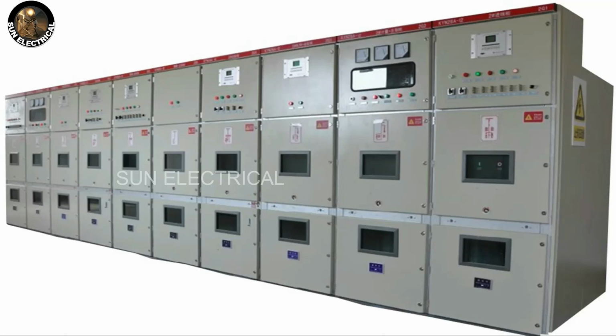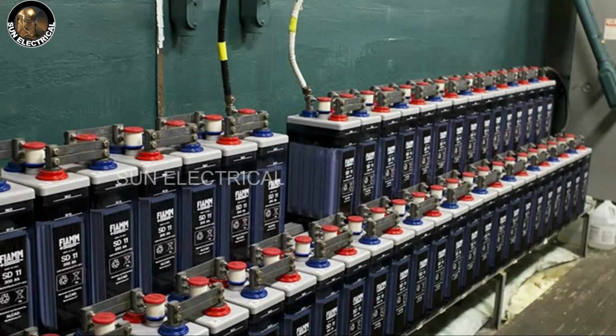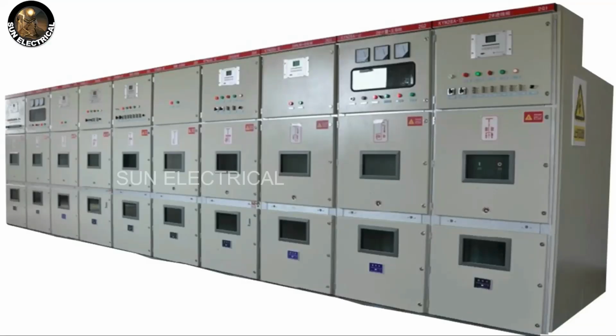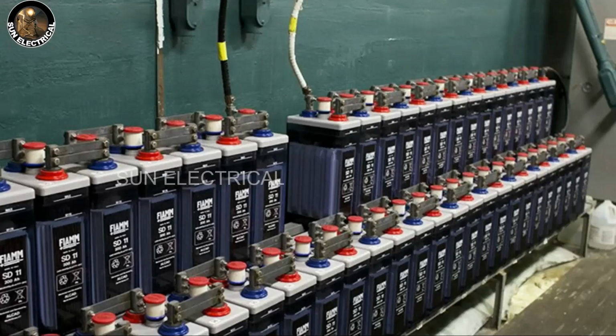And the second one, static devices which need DC supply can be connected directly to the batteries, but when AC supply is used, a rectifier circuit is needed. That means bridge rectifiers, separately, for some lamps, that means LED lights. And third, control circuits consist of many digital devices, such as digital displays.